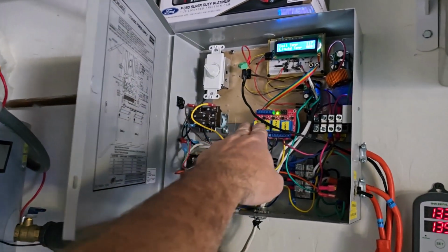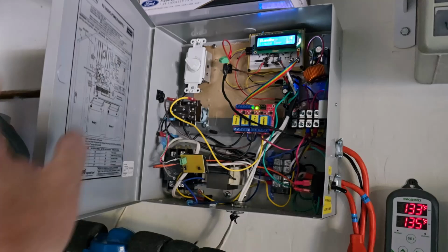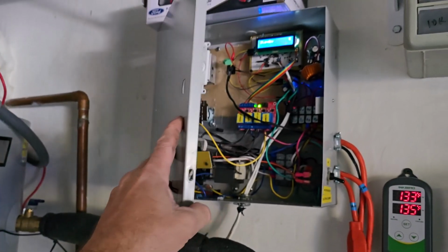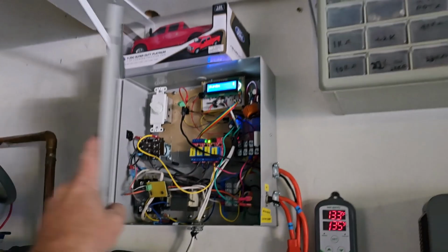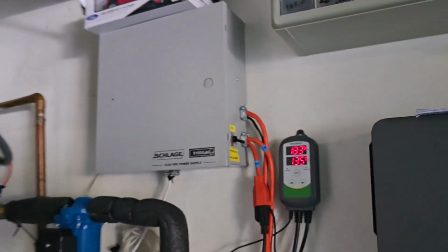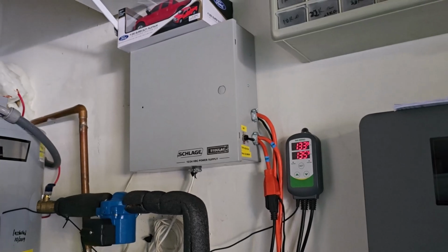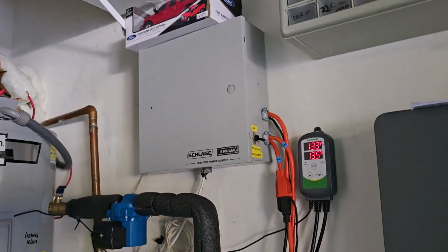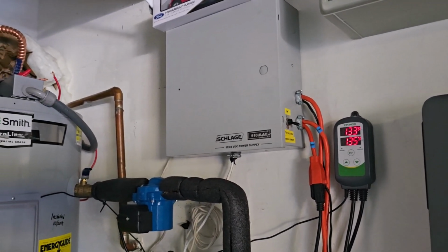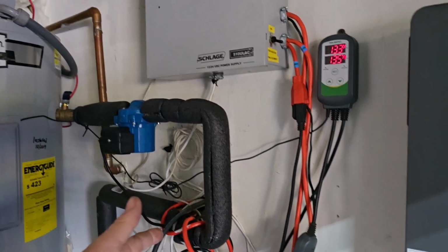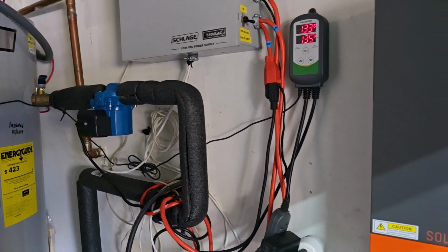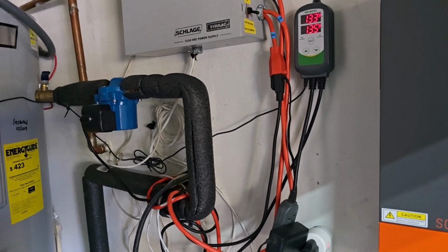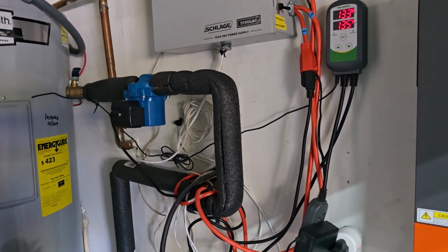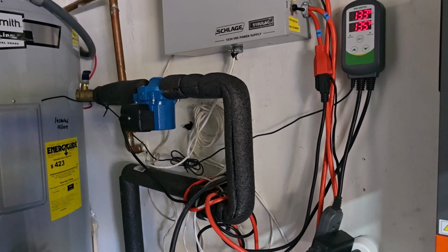So I have 2-speed relays on the pump, for low speed and then high speed. I set it in my controller so 100 degrees kicks it on low speed, and once that liquid line gets over 110 degrees, it goes to the faster speed. And that's been working. It's like having a thermostat on your boiler, because you don't want to ever just pass cold water right through it. It's going to take forever to get the boiler hot, and you're not going to get good heat rise.